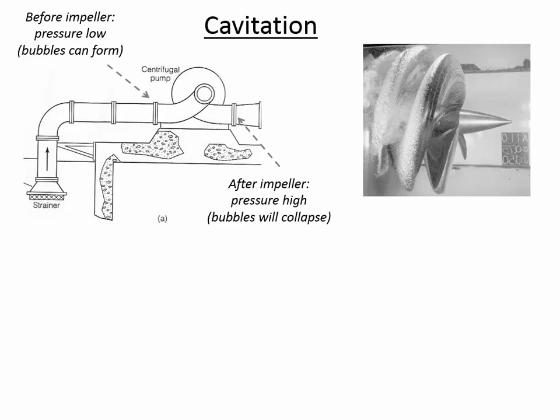The other way to boil water is not to heat it up, but to apply a vacuum, so that if the atmosphere that surrounds the liquid has a pressure lower than the vapor pressure, then little bubbles will form. And you may think, well, little bubbles aren't going to cause trouble. What's the issue? These tiny little bubbles, when they get onto the pressure side of the pump, collapse and send a shock wave through the water.